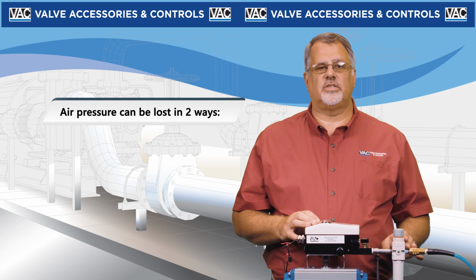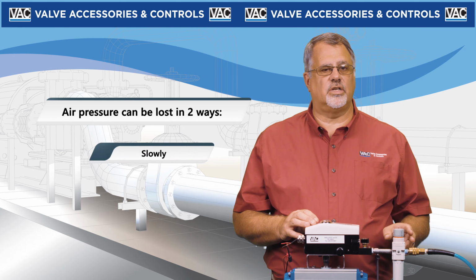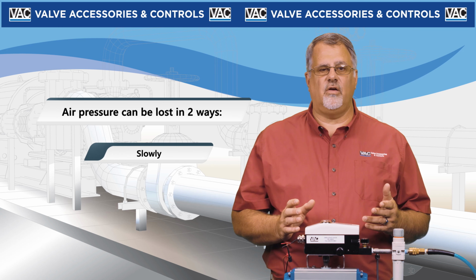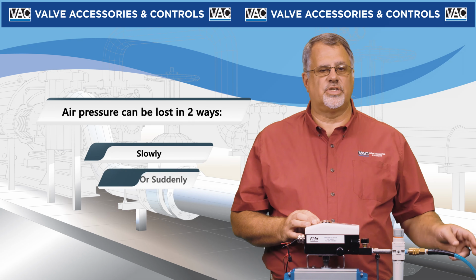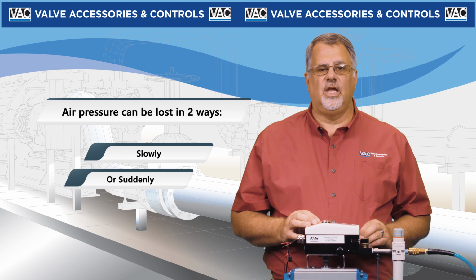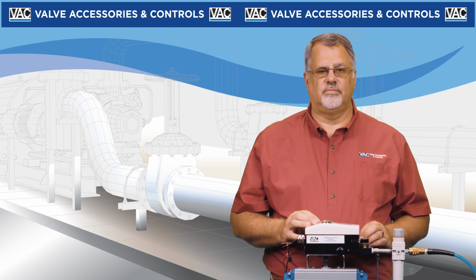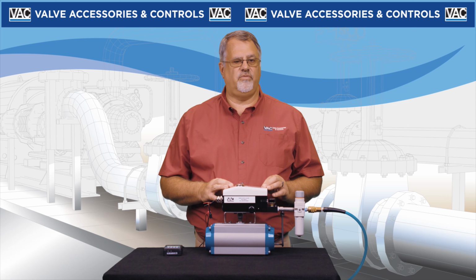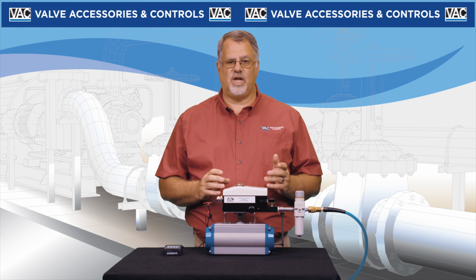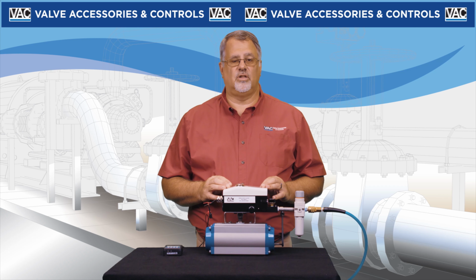Air pressure can be lost in two different ways: slowly, such as during a compressor trip or an air header leak in a remote location, or suddenly, such as an airline failing at the positioner supply connection. This is a standard configuration valve positioner set up as direct acting. 4 milliamps is closed in this case.